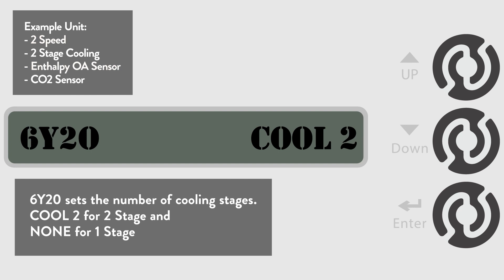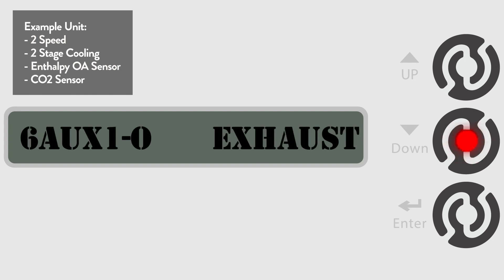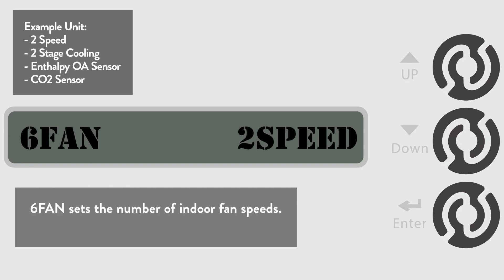For this example we will leave it at two cooling stages. Let's go to 6FAN. This sets the unit's fan speed. The default is 2Speed, and for this video we will just leave it there. But it can be changed to single speed, 2Speed, 3Speed, or VFD for variable speed if needed.